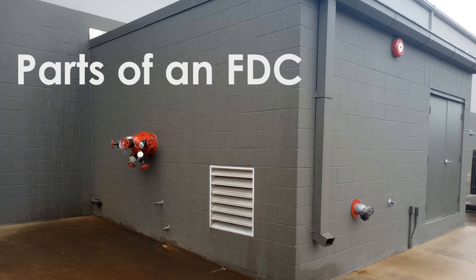In this picture, you see a portion of the building that extends outward that is typically used for a fire pump. An indicator that this is a fire pump, in addition to the fact that it sticks out, is the test header. On the left side, we see 1, 2, 3, 4, 5 2.5-inch connections, each worth 250 GPM, so that's a 1250 GPM fire pump.